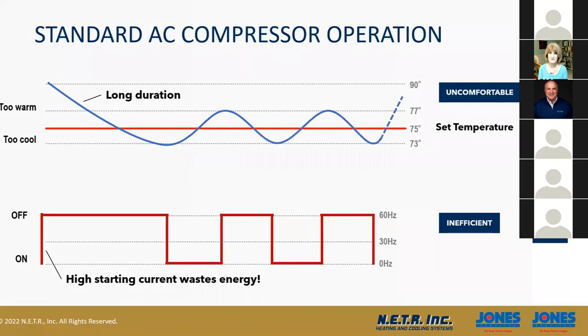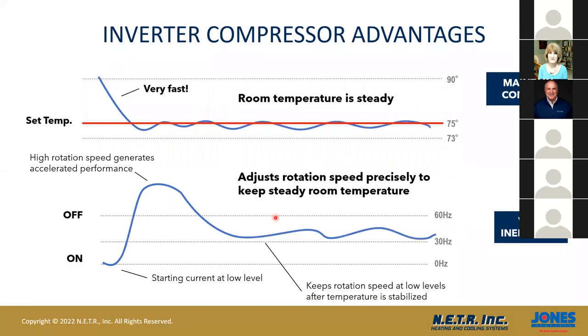So I want to talk about what an inverter-driven compressor is, because almost all air source heat pumps from Mitsubishi Electric or any of the manufacturers selling inverter-driven heat pumps right now work this way. The biggest difference is they start up at a very, very low current. If we look at the zero Hertz right here, they basically start at zero and ramp up. It's almost like an accelerator in your car. It speeds up and slows down the compressor. It doesn't turn on and turn off. As it speeds up, it brings the temperature down quicker or brings the temperature up quicker, depending on whether you're heating or cooling. And as it reaches the set point of the room, you can see what happens.